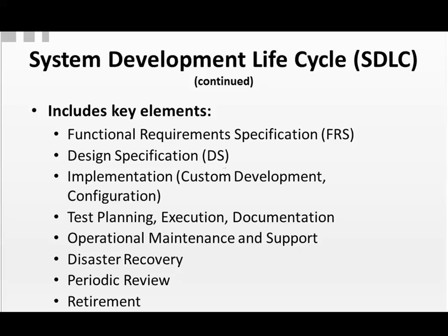You need to have a configuration specification that details the configuration of the system right before you're going to test it for validation. And that configuration has to be maintained. All of these documents must be maintained as living documents. If you change the requirements for your system at any point in time, before or after validation, you must go back and update these documents.